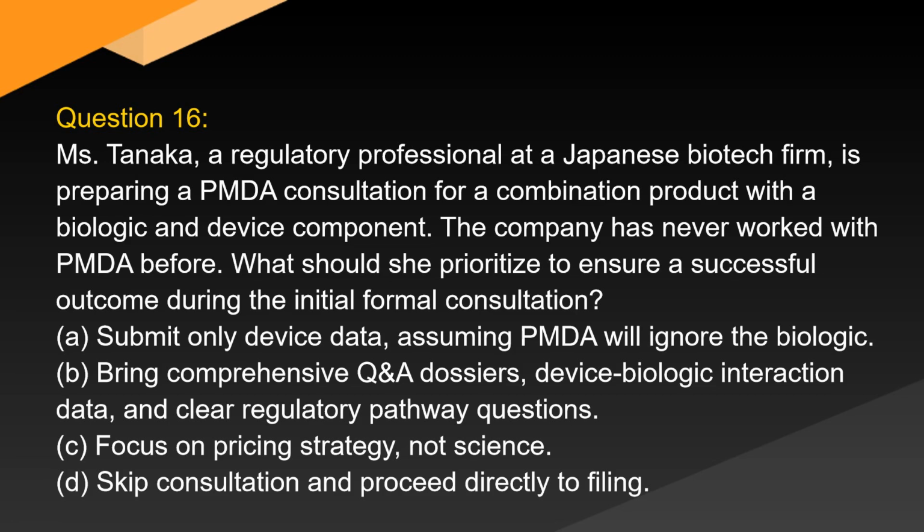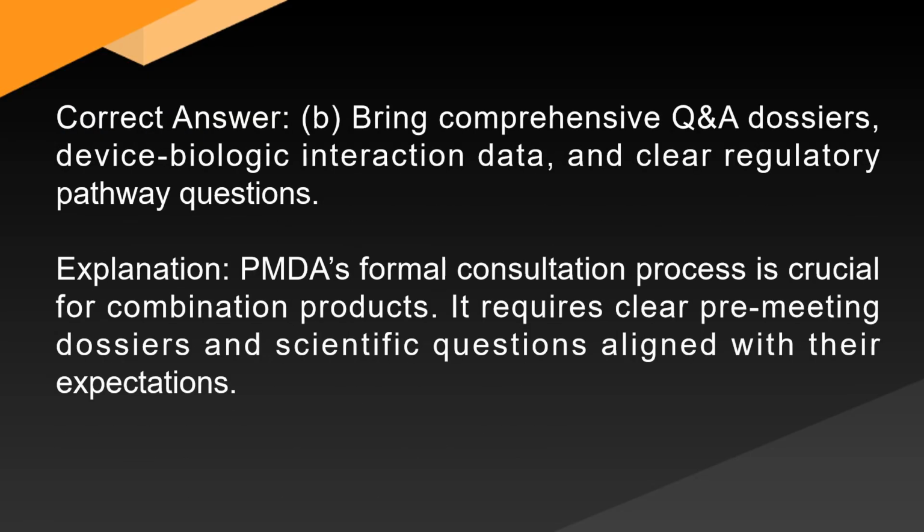C. Focus on pricing strategy, not science. D. Skip consultation and proceed directly to filing. Correct answer. B. Bring comprehensive Q&A dossiers, device-biologic interaction data, and clear regulatory pathway questions. Explanation. PMDA's formal consultation process is crucial for combination products. It requires clear pre-meeting dossiers and scientific questions aligned with their expectations.